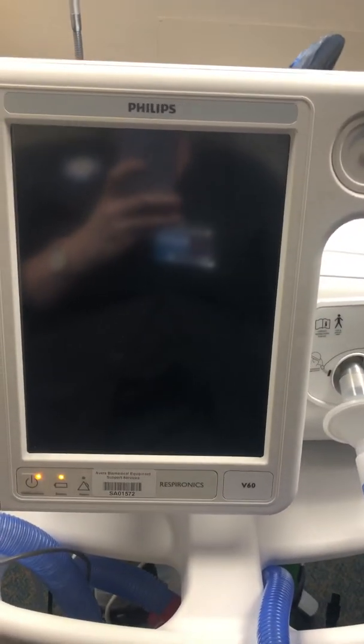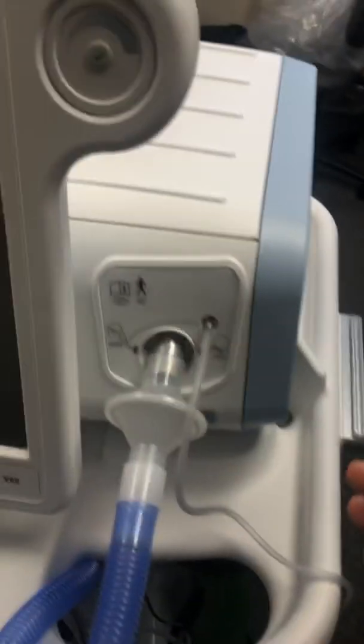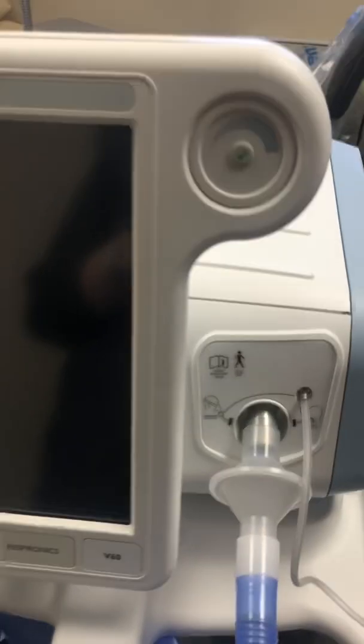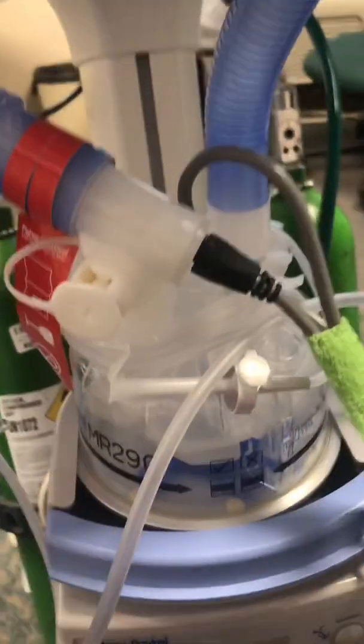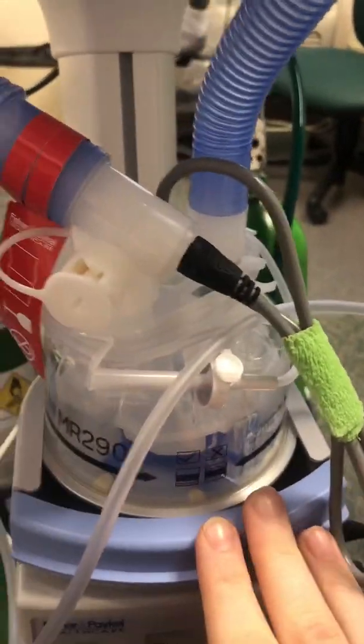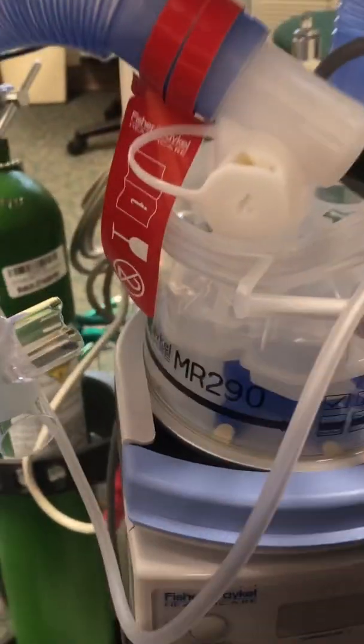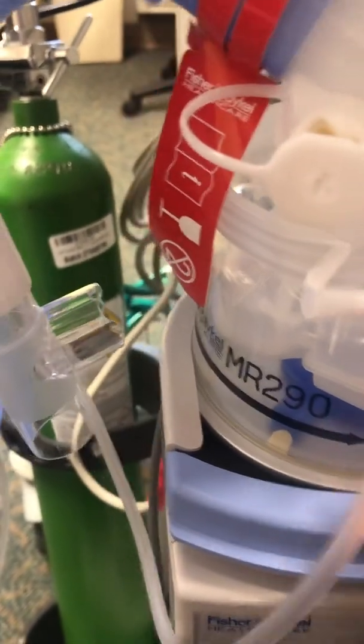So this is the user interface portion of the Bipap, and once we go through all of the other external features, we'll turn that on and I'll show you how to change your settings. If we look here, this is what's responsible for the pressure, and then we have this Bipap set up for heated humidity. This corrugated tubing goes to this Fisher-Paykel heated system. With this type of situation, we have this little spike here, and then we're going to spike the bag, and we use sterile water for inhalation. We'll spike that bag, and that'll get hung up here on the top.